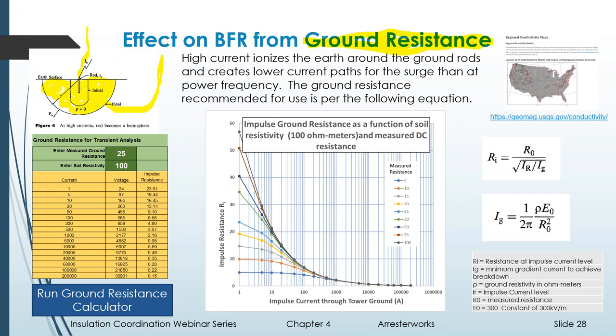So in this graph here in the center, you can see that if you have a measured resistance of say 25 ohms, that's at very low currents. Once you're up to 10 amps, it's already down to less than 20 ohms. Once you get up to 1,000 amps, the ionization in the soil has taken over and you're down to just a couple of ohms.